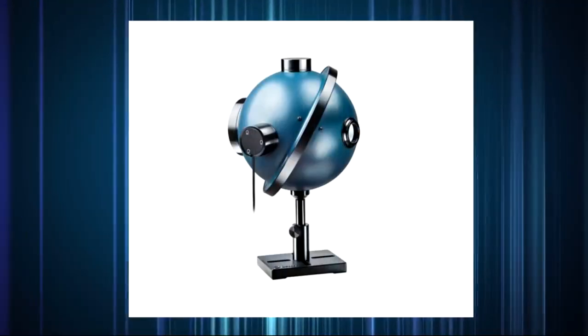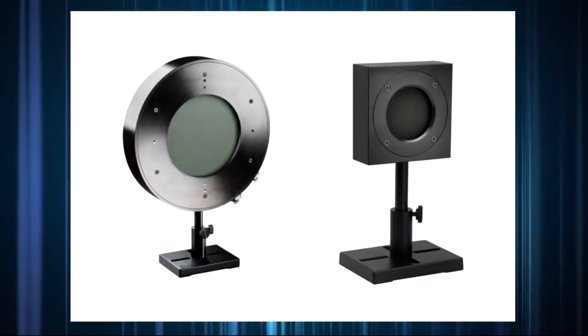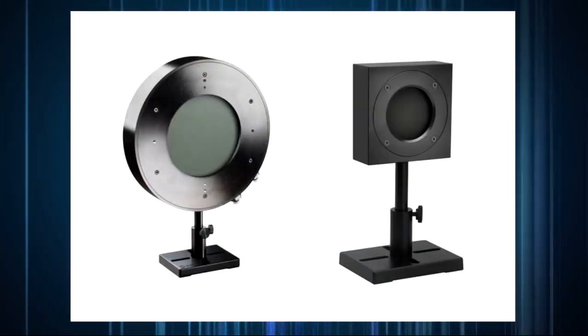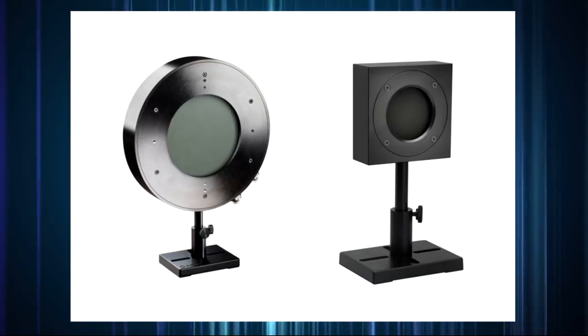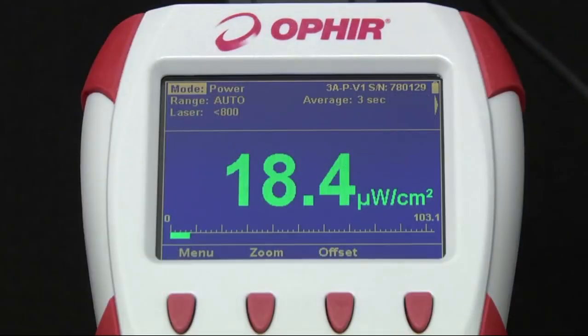For measuring divergent beams, there are 3 approaches. First is the integrating sphere, which is designed to capture all the light that enters it. Next is to simply use a sensor with a very large aperture and place it close enough to the light source to capture all of the power. Finally, you can capture only part of the beam, and then instead of total power or total energy, you'll be measuring power or energy density. Each of these involves some technical considerations, but that's for other videos.